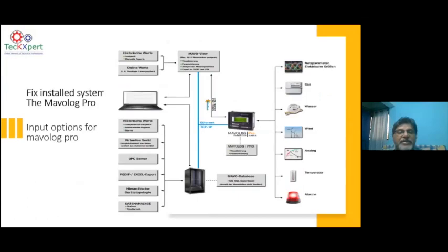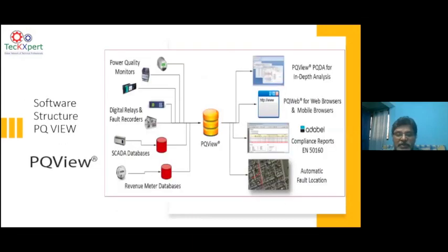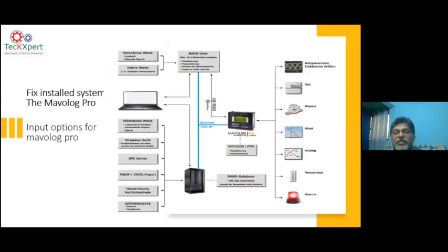With these sorts of power quality meters, you can connect analog signals and digital signals. You can give CT and PT inputs, and you can remotely log it and all that. Now, this is all about continuous real-time power quality monitoring, and I'm talking about fixed meters. The other option is portable analyzers, but when you use fixed meters, you can always do waveform capture and waveform analysis. Before a fault happens, you will be able to find out that a fault is developing or that something is aging. For example, if an OLTC is not working properly, you get to know about the OLTC failure only when it has failed.